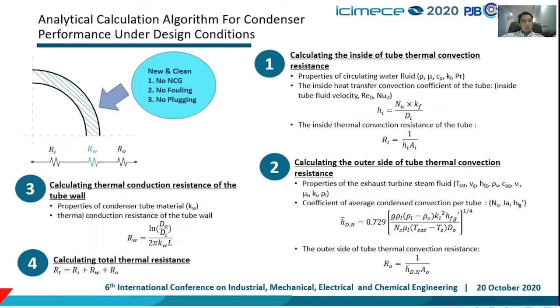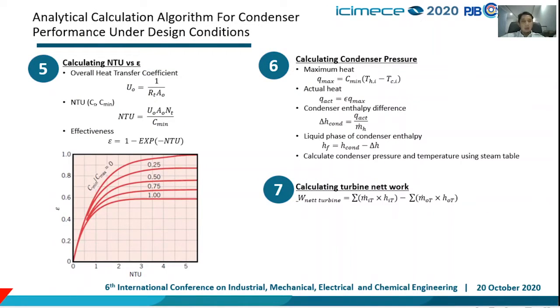This is the analytical calculation algorithm for condenser performance under design condition — new and clean, with no non-condensable gas, no fouling, and no plugging. We calculate the inside-tube thermal convection resistance, outside-tube thermal convection resistance, thermal conduction resistance of the tube wall, and total thermal resistance. Then we calculate NTU, effectiveness, condenser pressure, and turbine net work.